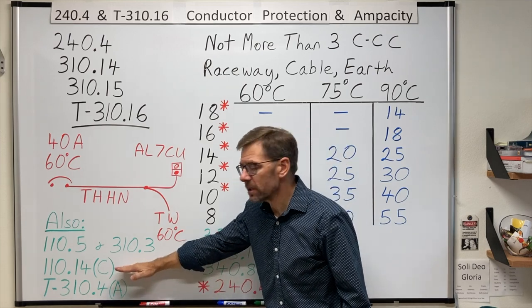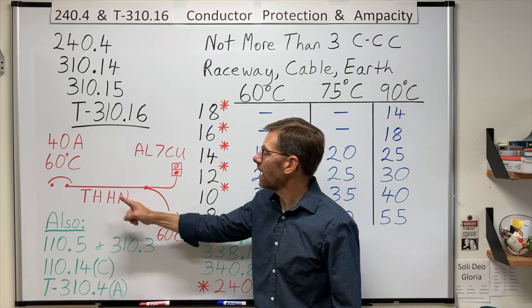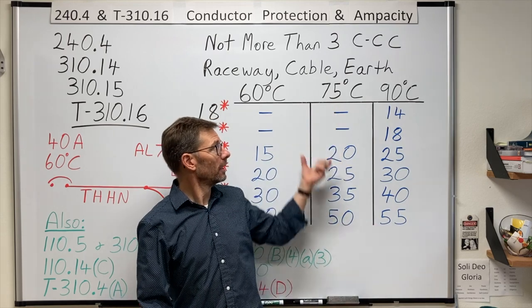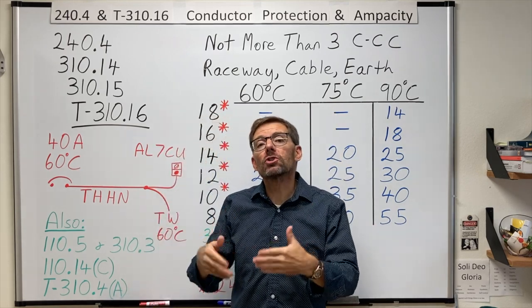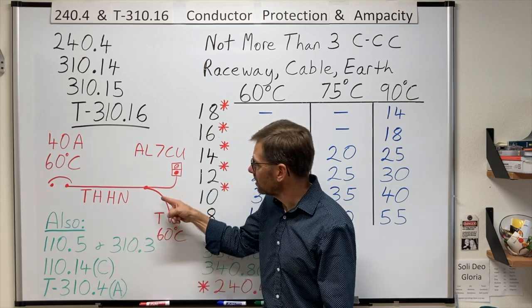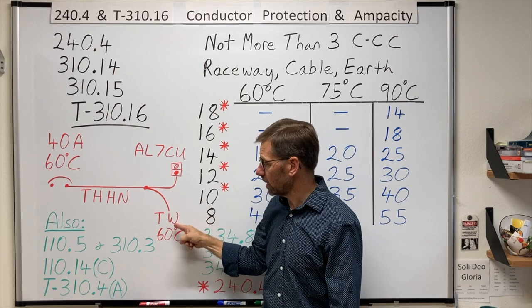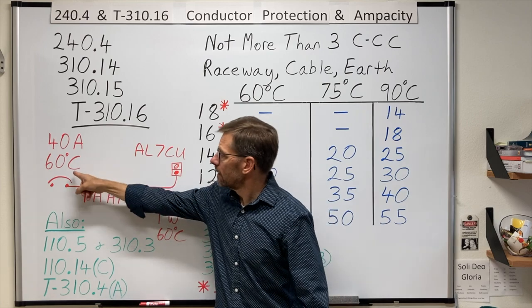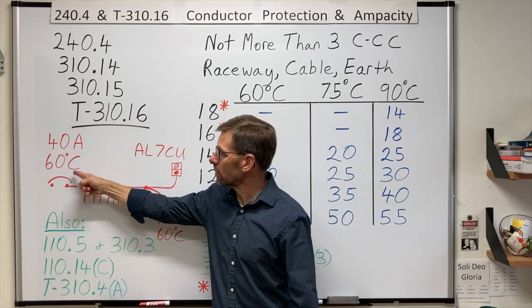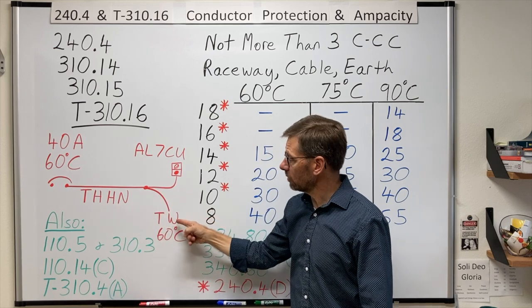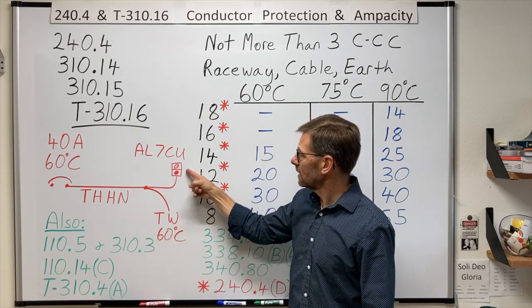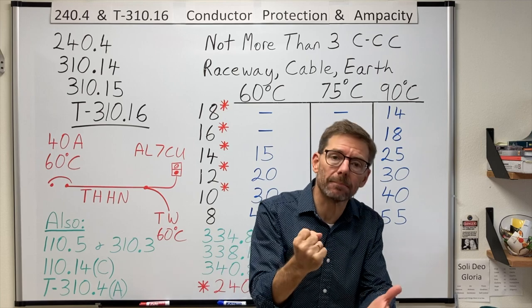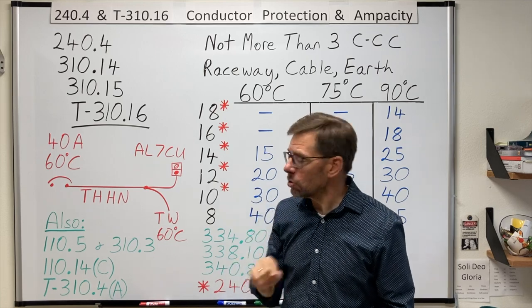So what 110.14c tells me is that I have to pick an ampacity for this wire, from the column with the lowest rating of any connected termination, conductor, or device. In this case, I'm looking at 60 degrees. The breaker is rated for 60 degrees. This connected wire rated for 60 degrees. And this, well, this lug, what's this? So you don't generally see a temperature rating stamped on a lug. But what you do see is something like this. It lists the types of metals that the lug can be used with, aluminum or copper.